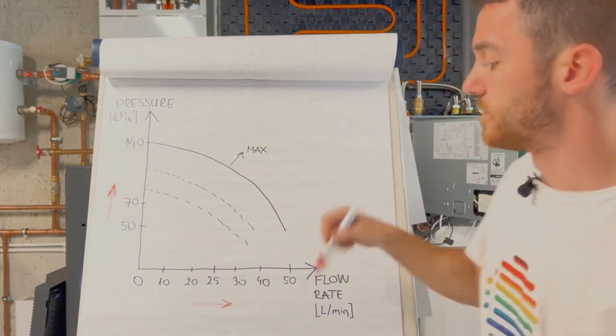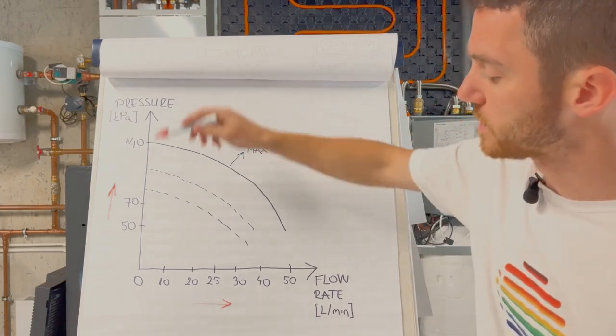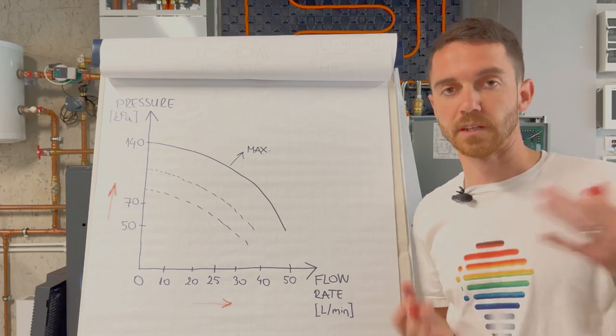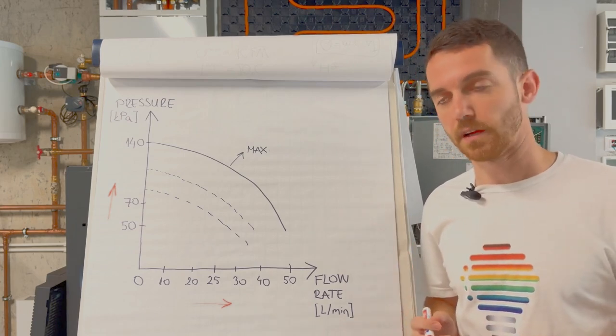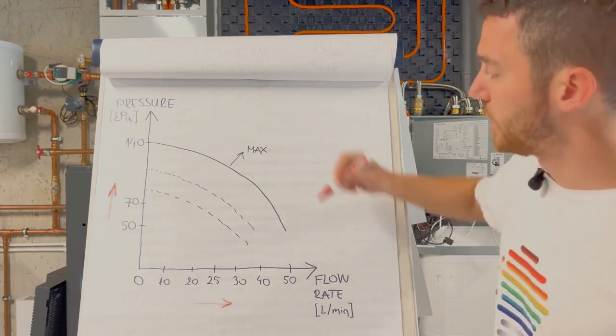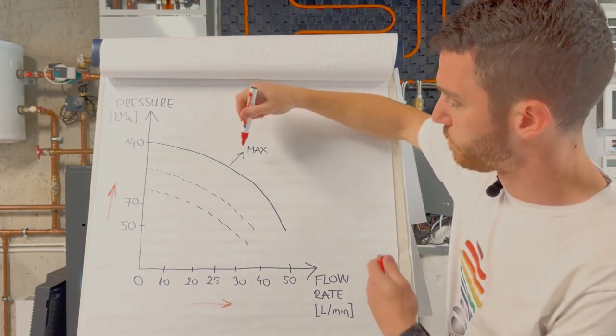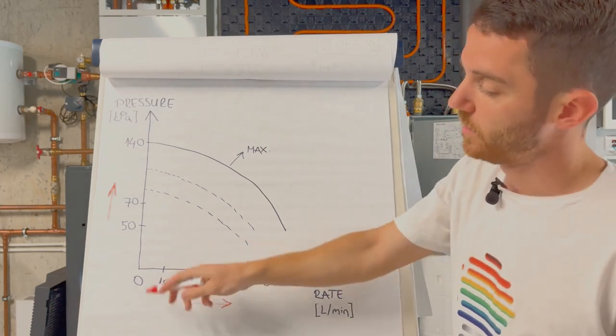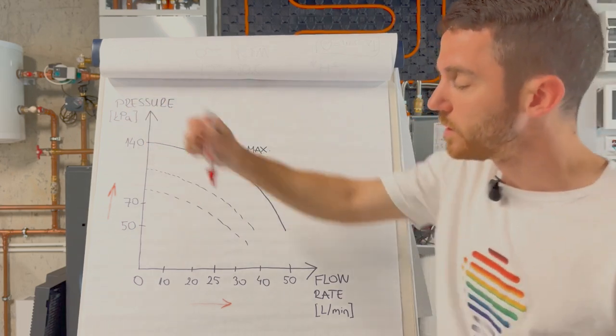We have less pressure drop available for our installation, and the same is vice versa. What I mean, available pressure drop on our installation, because this curve is only for installation. It means that internal pressure drop like heat exchanger, pipes, valves, all are already calculated. And let's see what we have here available. This is maximum curve, so maximum available pressure drop is around 140 kilopascal for zero flow rate. For 10-20 it's like something around 100.